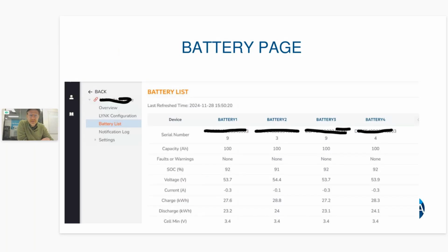And then we're really interested in this battery list here, which tells you what's happening with each individual battery: the state of charge, the voltage, the throughput. So you can see charge and discharge kilowatt hours here, so you can see if one battery is working harder than the others. And that's going to give you an indication long before the customer has a problem that maybe something's not right.